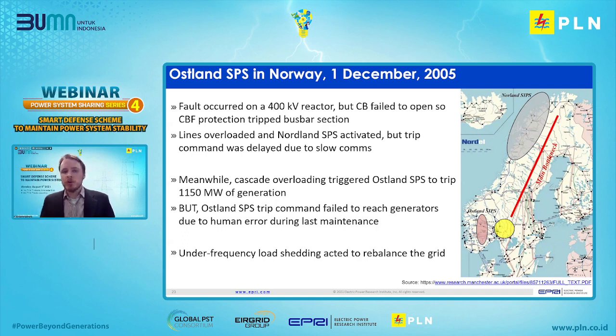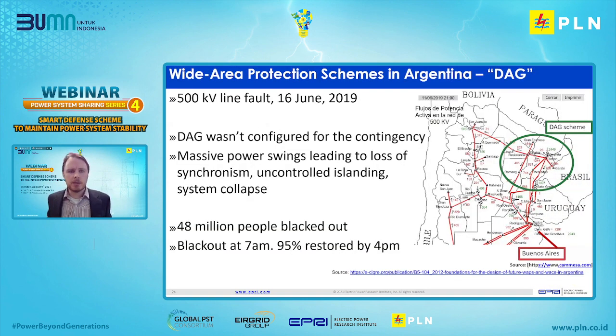So this overload was allowed to persist and caused cascade tripping of a number of generators, and this led to the east, the Ostland SPS, also tripping. So now both schemes have operated, and this resulted in almost 2.4 gigawatts of generators being lost. This caused a significant underfrequency event and required load shedding to rebalance the grid. So this was a case where there was quite an advanced interaction between the issues, and why it's important to study their interaction. Just moving to the next example.